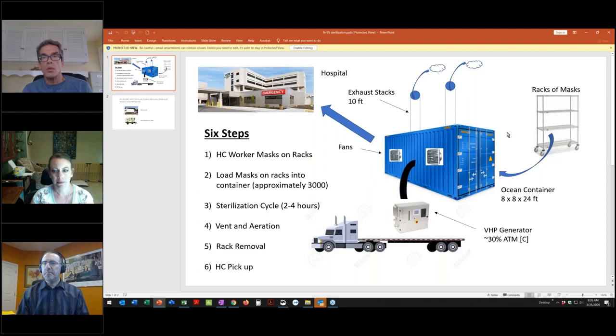The cycle is pretty simple. It's 6 steps, as you can see on the left. The idea would be to have healthcare workers who are already exposed and potentially at risk bring their own PPE out, load them onto racks for masks and a variety of other PPE that can be reused, load those into the chamber, commence the sterilization cycle, load the atmosphere in the chamber and soak it, run it through venting and aeration, and then opening the chamber, removing the racks, and making those available to the same or shift healthcare workers going in and out of the building.